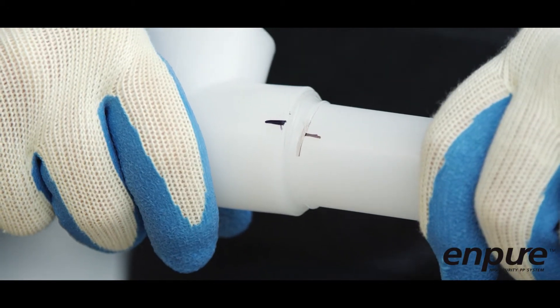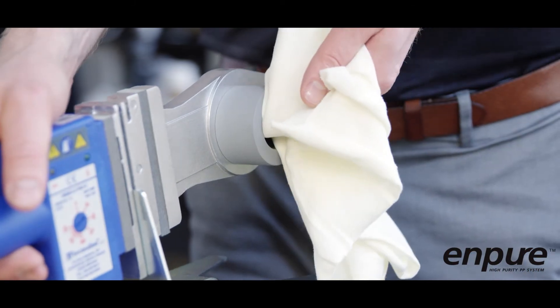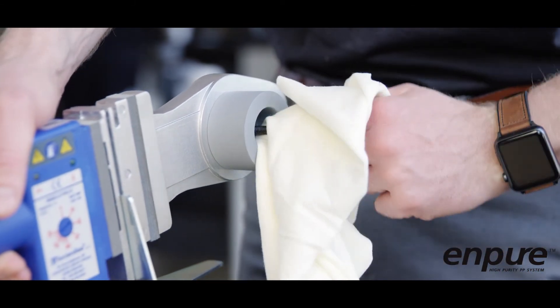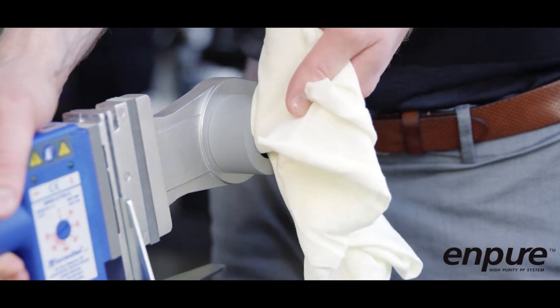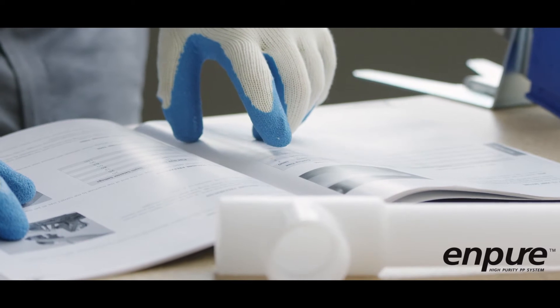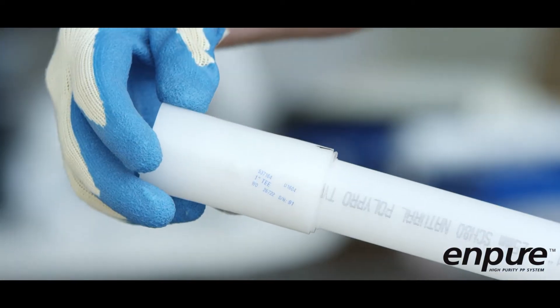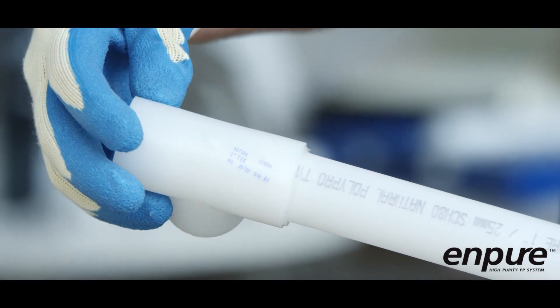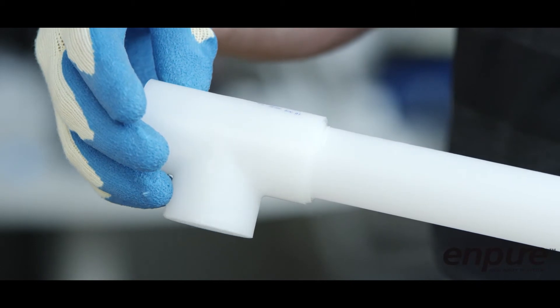Ensure the longitudinal reference lines of the pipe and fitting are perfectly aligned. If large amounts of material are left on the heater bushings, this suggests that the procedure has not been carried out correctly or the heating tool temperature is incorrect. Hold the joint together for the welding time specified in the table in the Enpure technical manual to allow sufficient time for the pipe and fitting to fuse together. If the fusion process was performed correctly, a uniform bead should be visible on the outside of the joint and a smaller uniform bead should be visible on the inside of the joint.